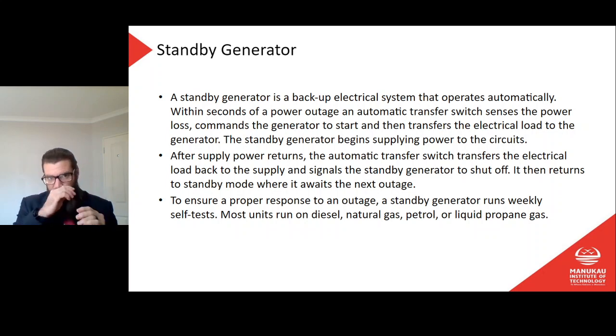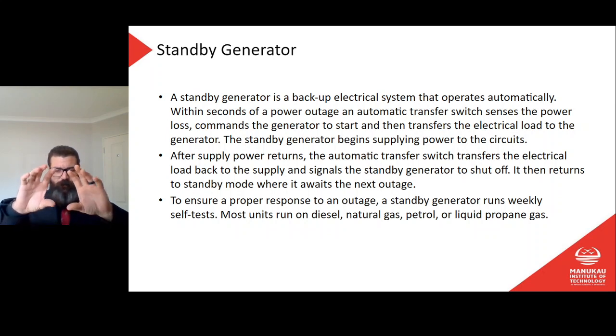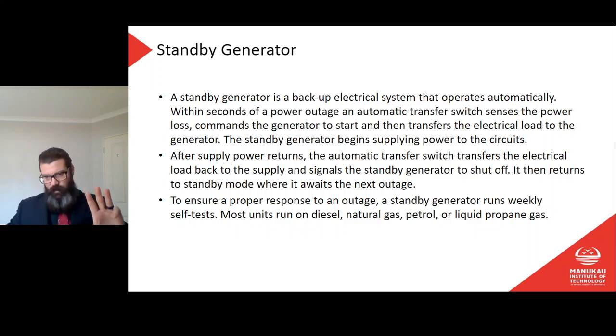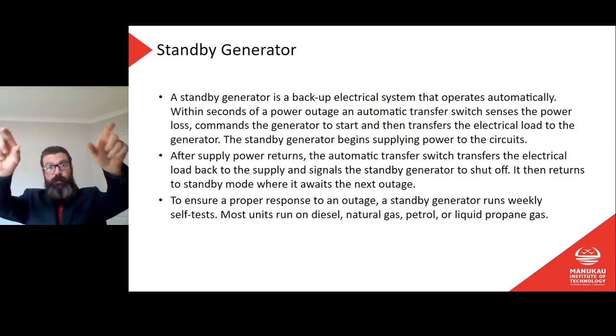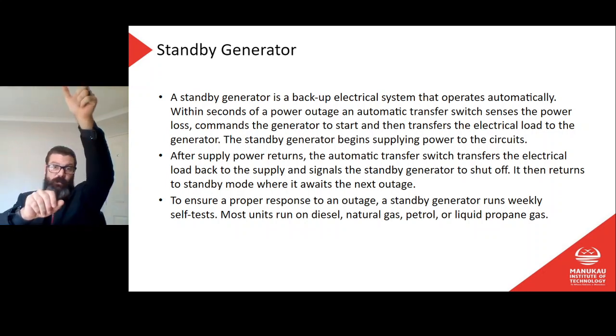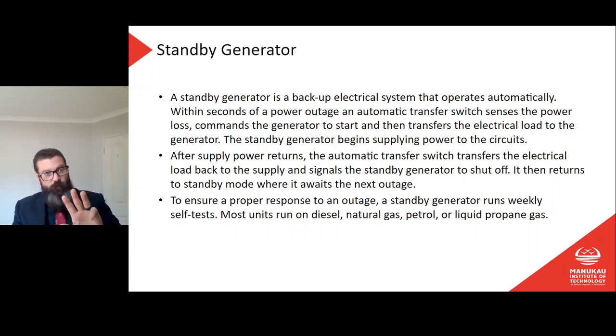How does that work? Well, it's kind of like what I was saying before with the UPS. We would have a couple of relays or contactors. If you can imagine a contactor that has two inputs, or no, let's say two contactors. One's got main supply coming in, one's got the generator supply coming in. On the outputs, those two are linked together, so we have one output that goes to the building. The contactor for the main supply is held on by the main supply. The contactor for the generator is held off by the main supply. So one would be a normally open and one a normally closed contact.